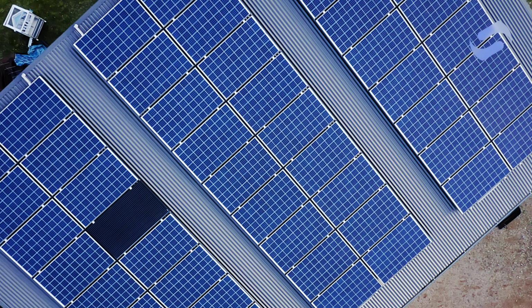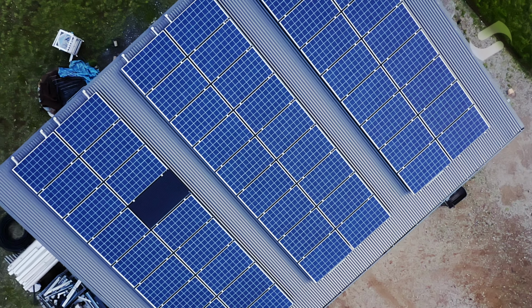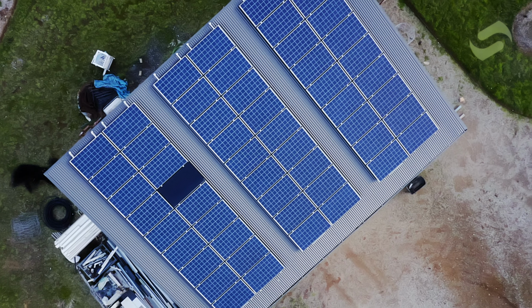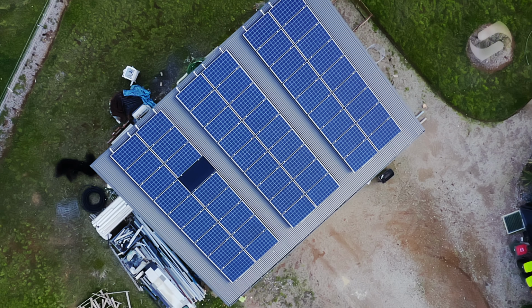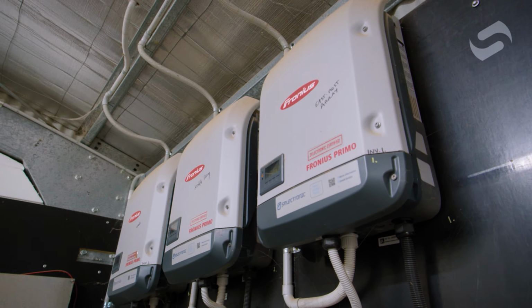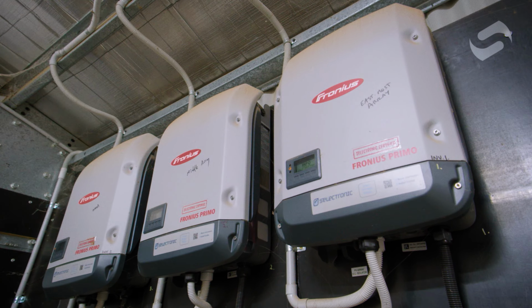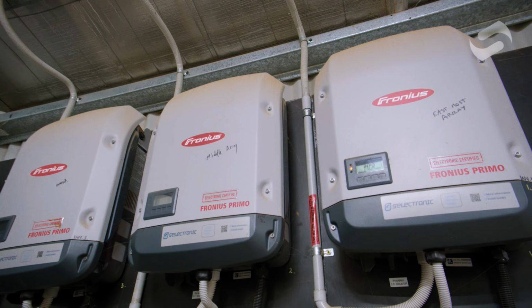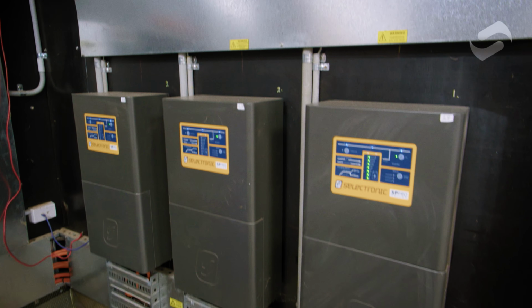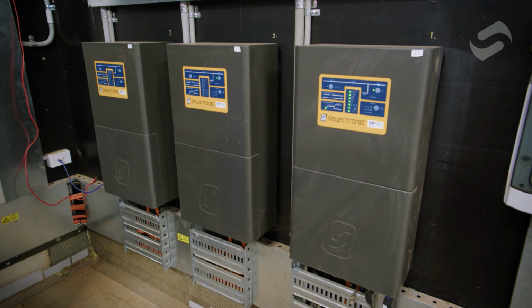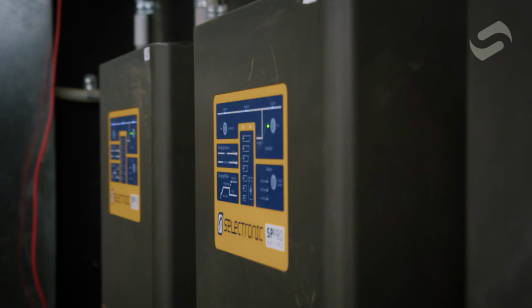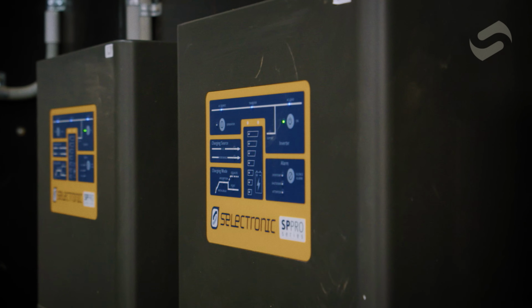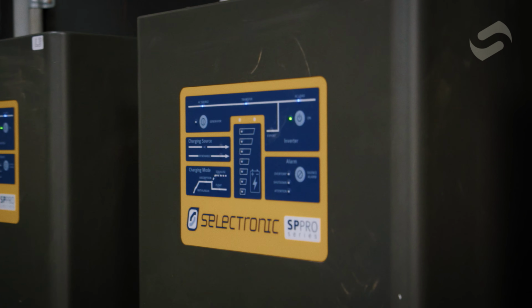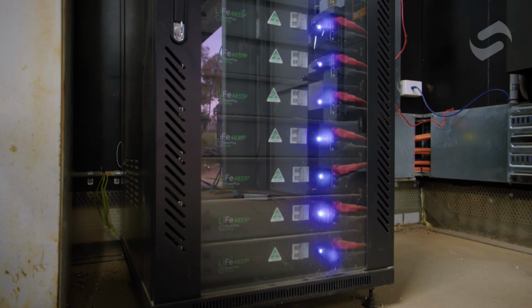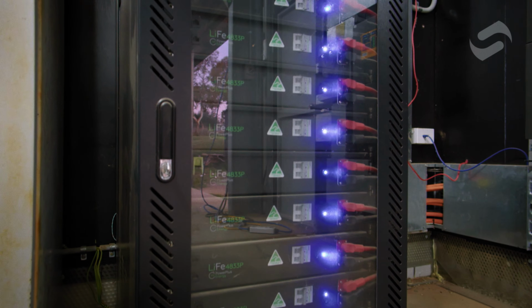We have a three-phase system. There are 3 strings of 5 kilowatts of solar on the roof, each connected to a 5 kilowatt solar inverter, feeding into 3 481 SP Pros - 5 kilowatts rated output each. Those 3 battery inverters see roughly 40 kilowatt hours of lithium iron phosphate battery, of which 80% is usable power.